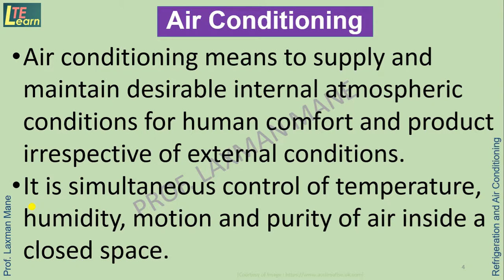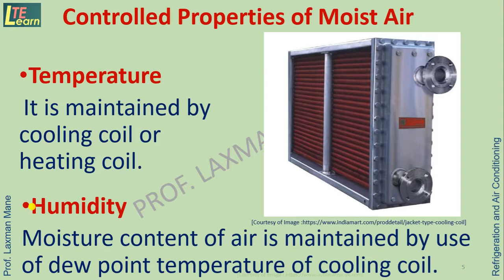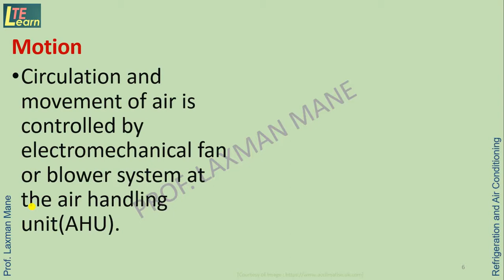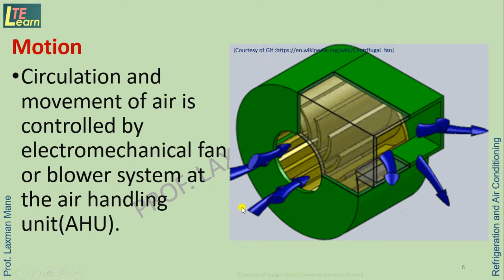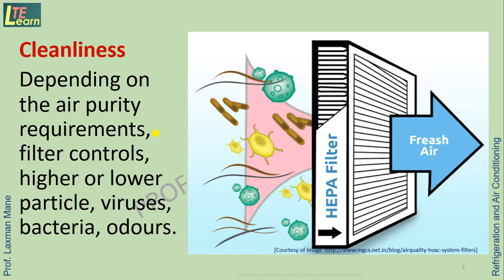Control properties of moist air are temperature, which is maintained by cooling coil or heating coil. Humidity, meaning moisture content of air, is maintained by use of dew point temperature of cooling coil. Motion, meaning circulation and movement of air, is controlled by electromechanical fan or blower system at the air handling unit. Cleanliness depends on the air purity requirements. Filter controls higher or lower particles, viruses, bacteria, odors, etc.